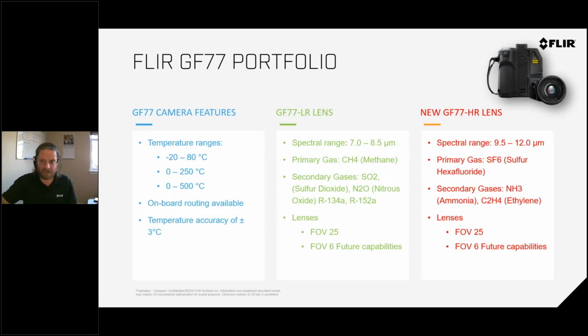Then we also have the HR or the high range lens. So the spectral range here is 9.5 to 12 microns. And then again, the primary gas is going to be your SF6, your sulfur hexafluoride. And then secondary gases: ammonia, ethylene, and a few others. And then again here, your lenses are going to be your 25-degree lens, which we have today. And then again, coming shortly next year, we'll have 6-degree optics as well.